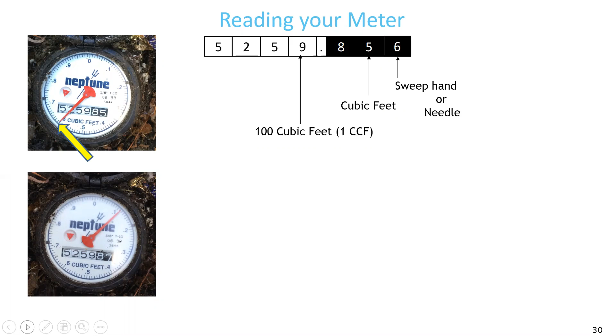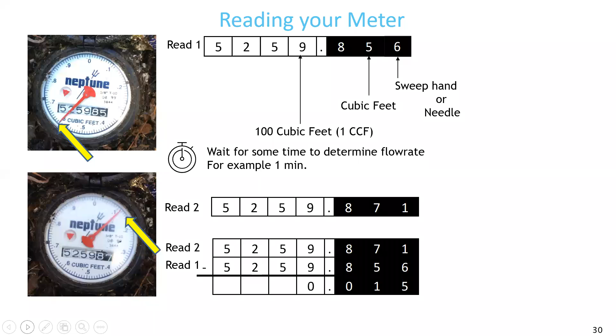If we were to wait a minute to see what our flow rate was in gallons per minute, next slide, we would have our next reading. This is the bottom picture on the meter here, 5259.871. We would subtract, advance please, the first read from the second, and get our total consumption, which we will convert into gallons here. Next slide, we have 1.5 cubic feet a minute, or 11.2 gallons per minute.